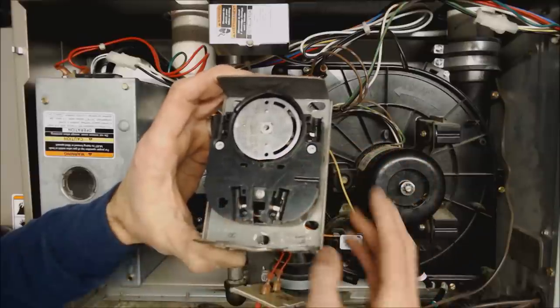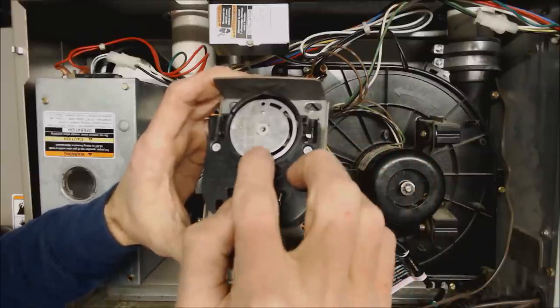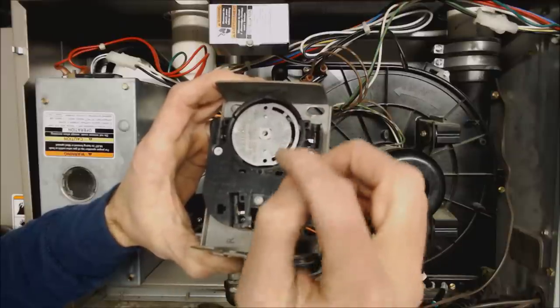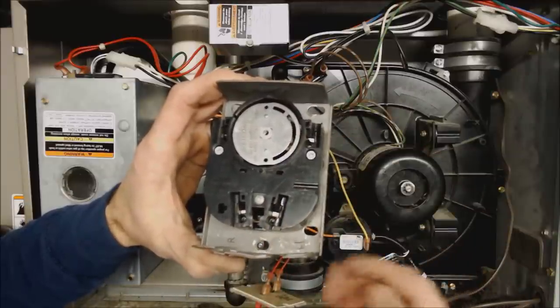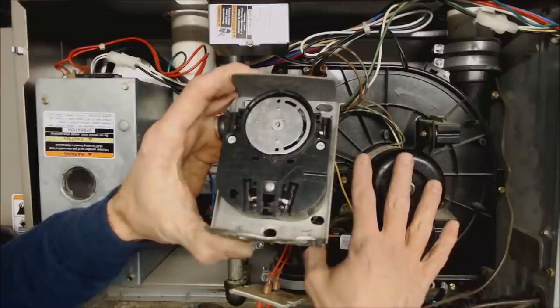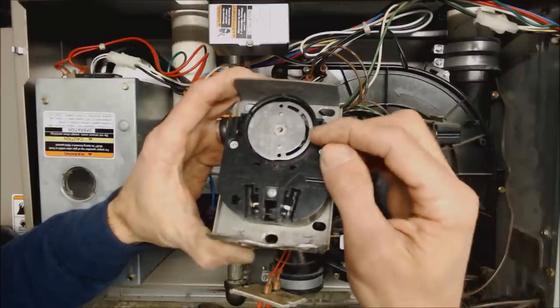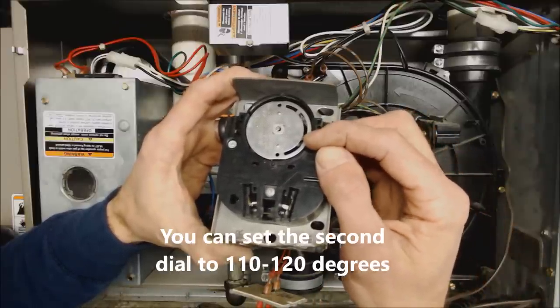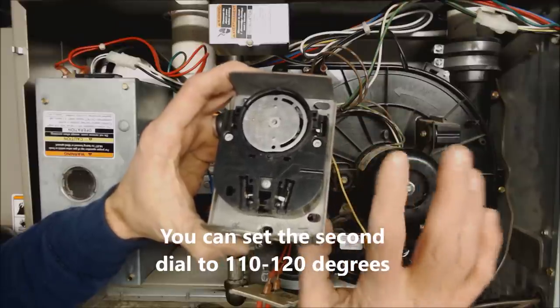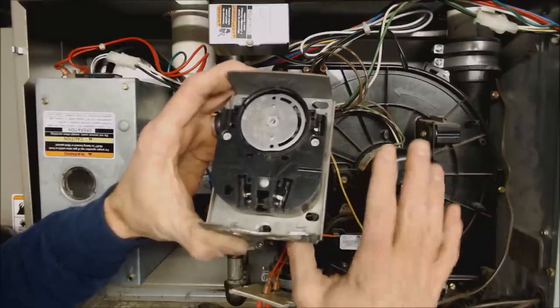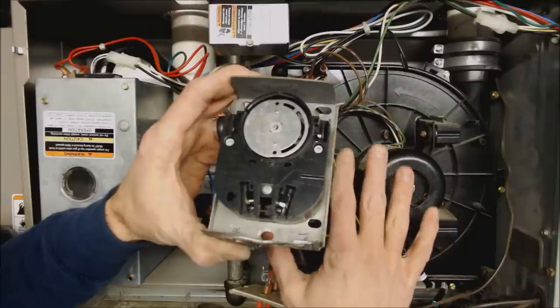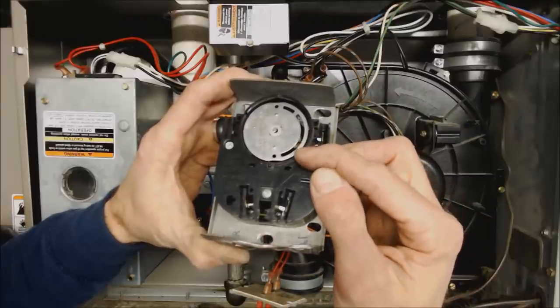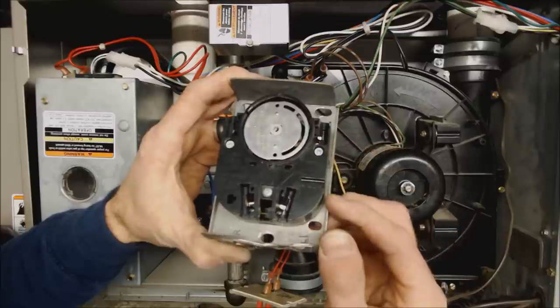So when your furnace is heating up, it's going to turn this dial right here and it's going to turn the blower motor on at say at 120. So when the ignition system is heating up the heat exchanger, the blower motor won't turn on until say 120 degrees. Then, when the thermostat is satisfied and the ignition system kicks off, the blower motor is still going to cool down the heat exchanger and it shouldn't shut off until 85 or 90 degrees.